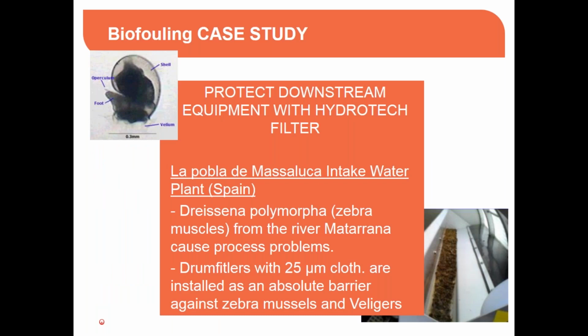So here are some case studies of our discfilter applications. This is from an installation in Spain. They had real trouble with biofouling. The zebra larvae were coming in. You can see the picture I have on the top left there. They're about 300 micron, but they can be as small as 30 micron. And then they get through the intake system, and then they would cause trouble in the cooling tower or wherever else they are, because they would develop. And so they installed the discfilter because it's an absolute filter, like an absolute barrier, and put 25 micron cloth on it.